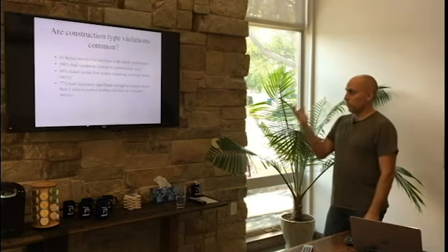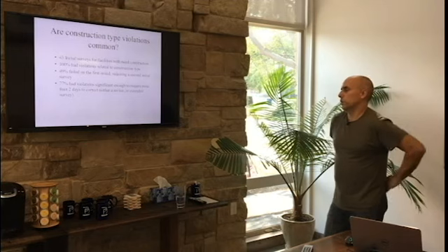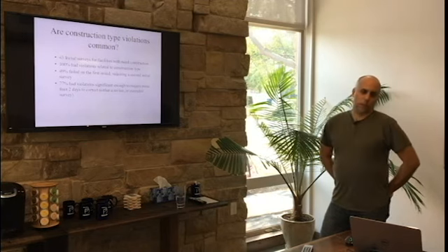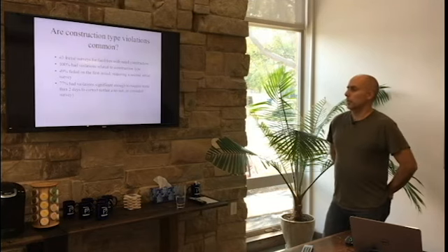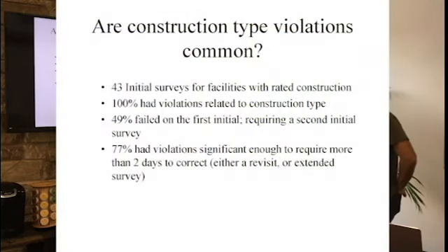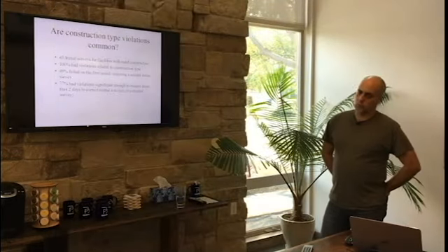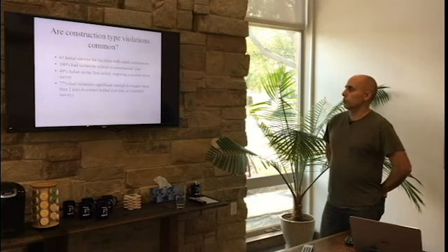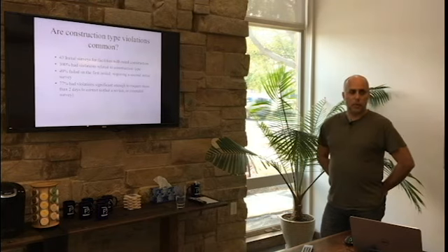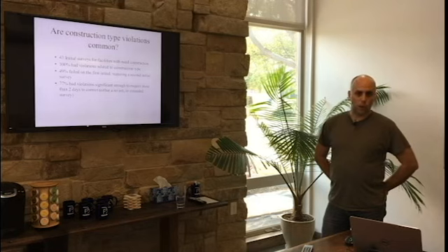Okay, so when I was a surveyor, I used this slide a lot to give some example of how bad this issue can get. And I did an 88 or is that 92? I can't remember anymore. Surveys total at the state. About 43 of them were initial brand new facilities. Some of them were second, some of them were smaller facilities, etc. But at least over half of those were initial surveys, facilities that had to be rated, 1 hour or 2 hour rated. 100% had issues.